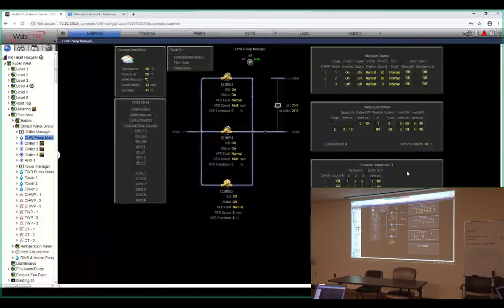So on pumps, if we get above 90%, that's where we stage up another pump. We drop below 40%, and that pump will be staged off. You're getting that reading off the drive. Getting that reading from the drive. Questions about pumps? Yeah, you got my head spinning. Power manager.